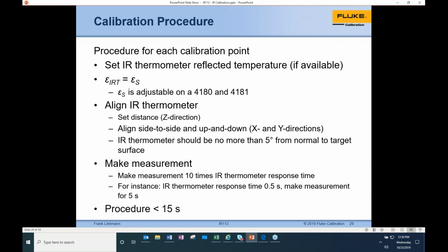With your guns and your IR sources, you always want to make sure they're the same. So if you're testing a 0.95 gun, you want to make sure your heat source is a 0.95 source. Again, the alignment, we're doing the XY. The Z direction, I can't remember if I got a slide on that, but this is more applicable to hand alignment. Even though you've got your X and Y, your up and down, if you tilt in or out or left or right, that can cause a deflection in what the optics are going to see. So make sure you're level. You want the optics up and level, straight on to the target, so you're not getting that deflection, and the entire optic is looking at the source.